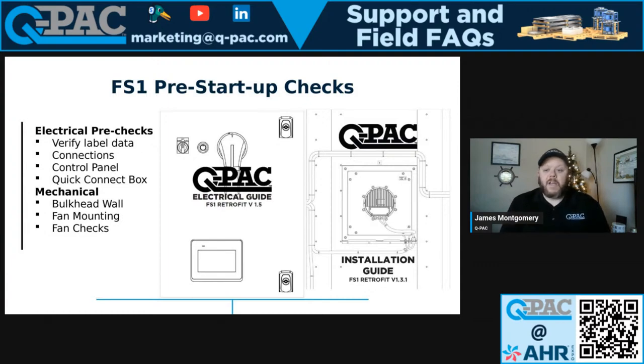So we're going to verify incoming power. That's high voltage, three phase, 460, 208, 220, whatever you've got. You're going to verify those connections. You're going to make sure that they're adequately sized. If you're unsure of what size you're supposed to be using, you can obviously refer to the NEC. If you've got the electrical trade on hand, they can help you pull up the NEC. But you want to look in our electrical guide and our installation guide. It's going to talk about what size knockouts you need and the minimum size cable requirements.